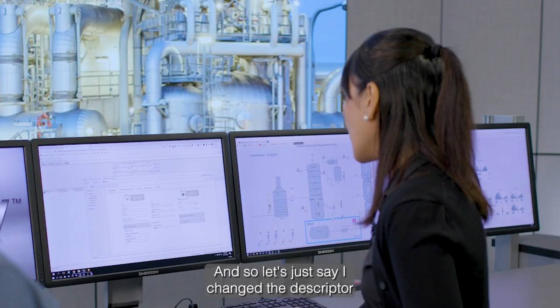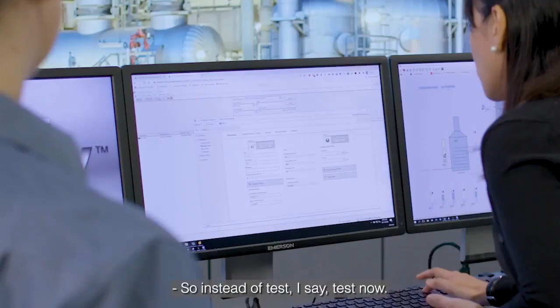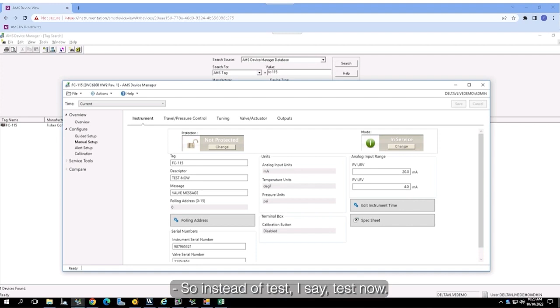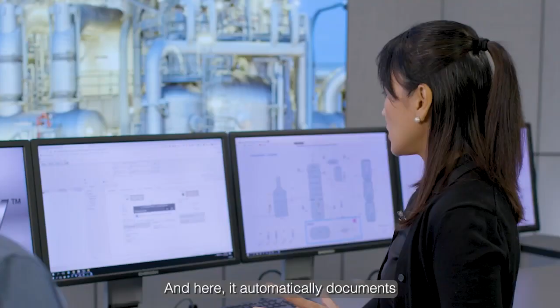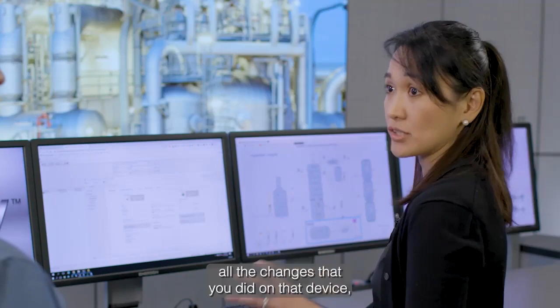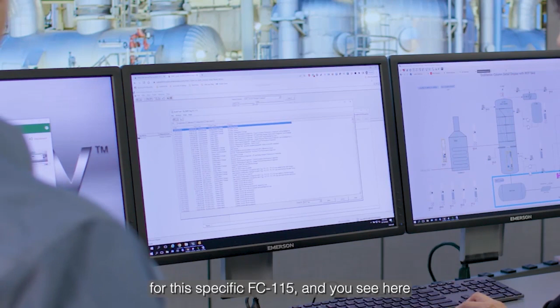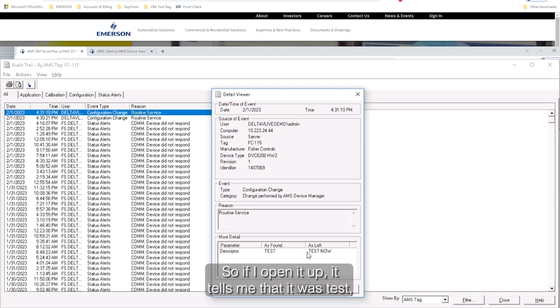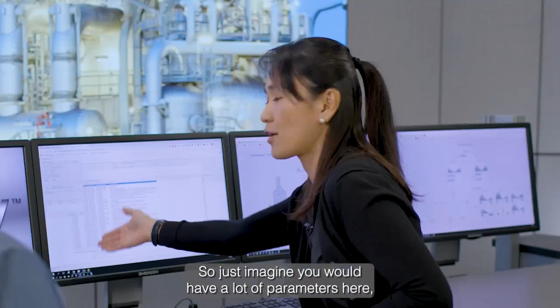Let's just say I change the descriptor on this device - instead of 'test', I say 'test now', and save that configuration change. It automatically documents all the changes you made on that device, so you don't have to manually write them down. I can open up the audit trail for this specific device and see that there was a configuration change just now. If I open it up, it tells me it was 'test' and now I changed it to 'test now'. Just imagine you'd have a lot of parameters here, and all those changes would be automatically documented.